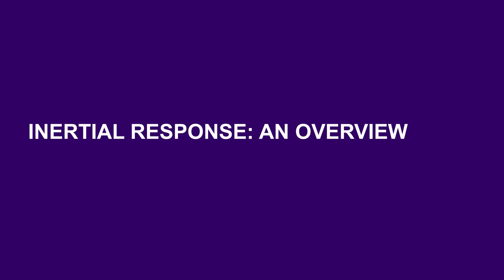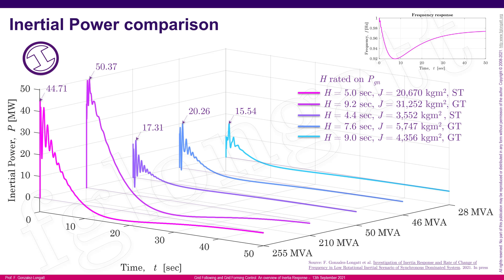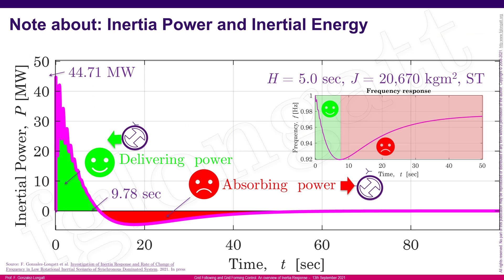Inertia response is the active power contribution that a synchronous machine delivers during an under-frequency event. The machine releases kinetic energy from the rotor, reducing speed while producing more active power — a positive contribution during under-frequency. However, during the recovery period, the machine starts to absorb power. When mimicking inertia response in power converters, this absorbing or recovery period must be carefully considered.